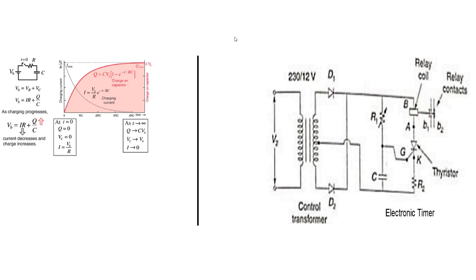Here you can see the coil of the relay and the common terminals. B1 and B2 are the normally open (NO) and normally closed (NC) type contacts. When the coil of the relay is energized, B1 will become NC from NO, and B2 will become NO from NC. Initially, B1 is the NO type and B2 is the NC type contact. This is how the on delay RC based electronic timer works.